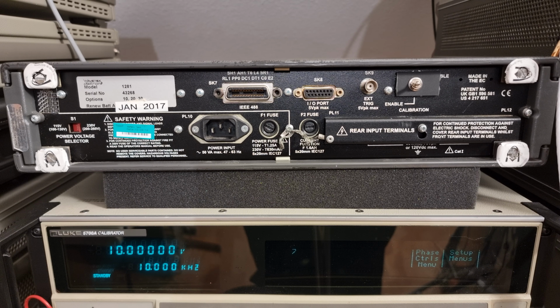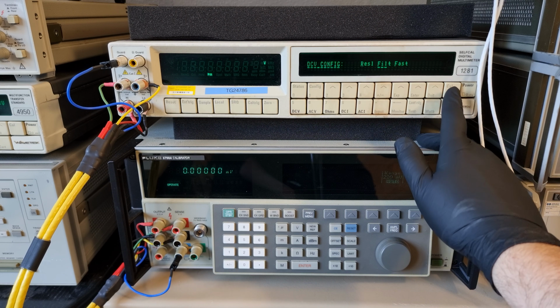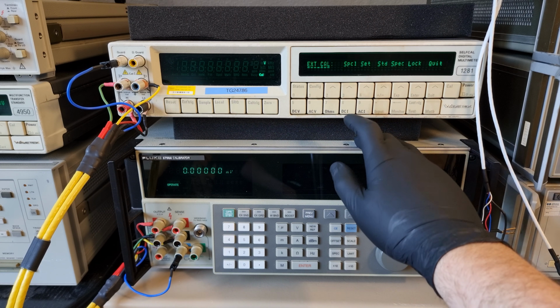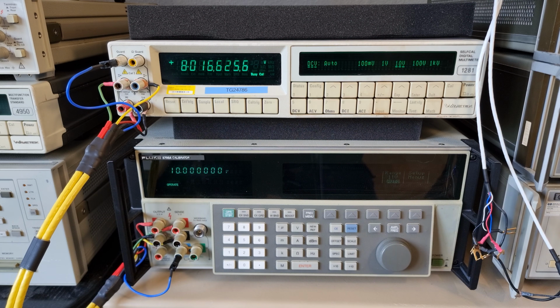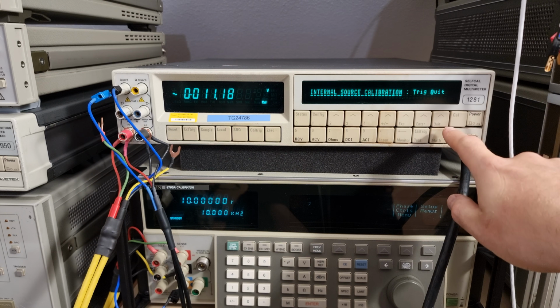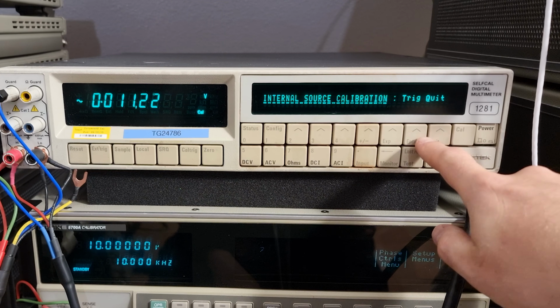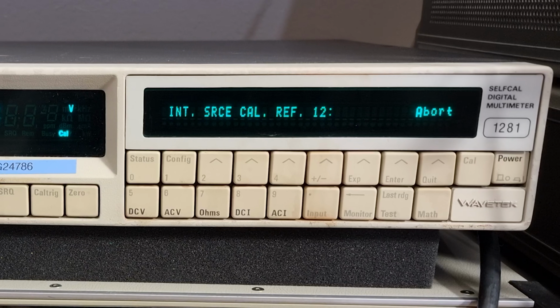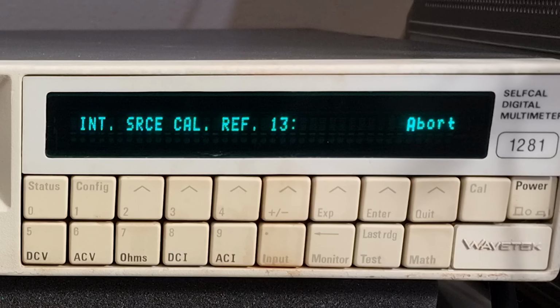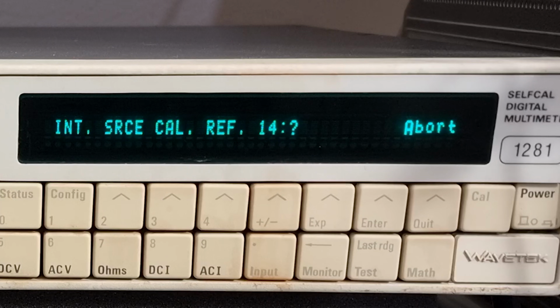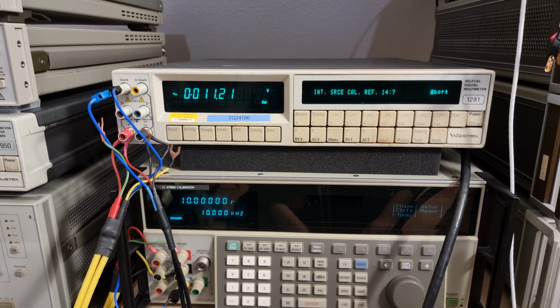Here's why. Let's say we send this to a cal lab. First of all, they are relieved that the customer didn't forget to include the key for what is usually the calibration enable key switch. They show our meter what a real 10-volt source is, and it adjusts its own gain and offset parameters. After that, the meter offers to use its newly adjusted faculties at their highest accuracy, to check on some built-in high stability standards and to memorize their values. In the future, it can use those again to realign its less stable parts and ultimately earn that self-cal title.